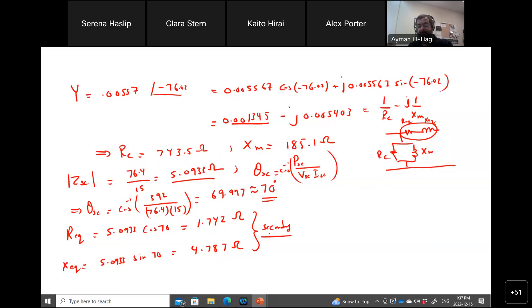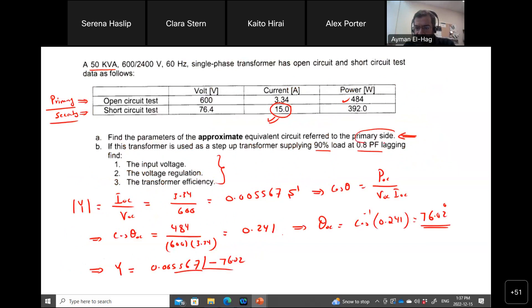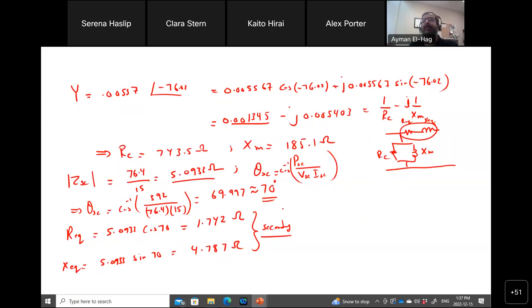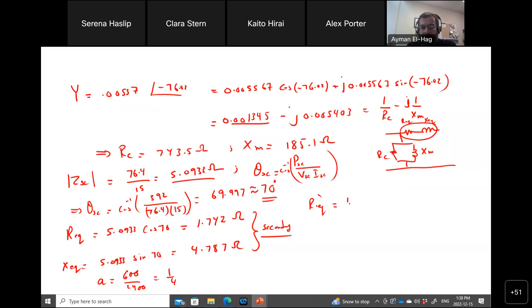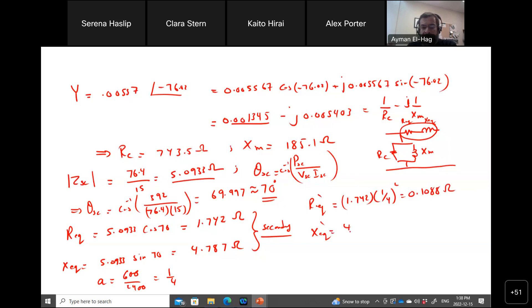But we want to refer them to the primary, because the question asks us to refer everything to the primary. So we multiply by a-squared. The turns ratio a equals 600 over 2400, which is 1/4 for this step-up transformer. So R_eq' equals 1.742 times (1/4)², giving 0.1088 ohms. And X_eq' equals 4.787 times (1/4)², giving 0.30 ohms.